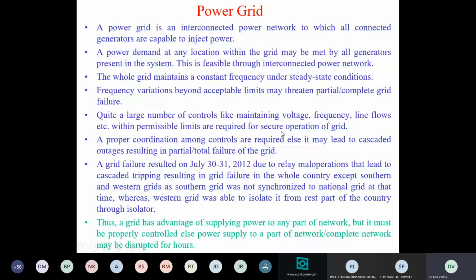One example was the grid failure which occurred on July 30th and 31st, 2012, and this was a case of failure of relay coordination. Due to malfunctioning of relays, it resulted in multiple, cascaded trippings, and that caused total darkness for nearly 2 days in almost the whole part of the country, except the western region and southern region.